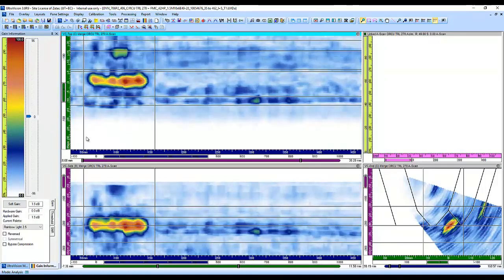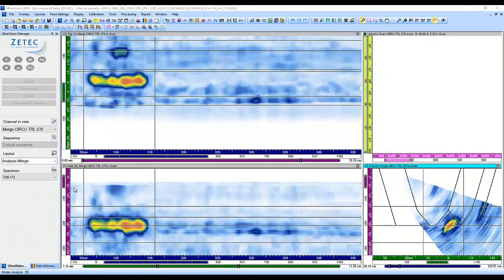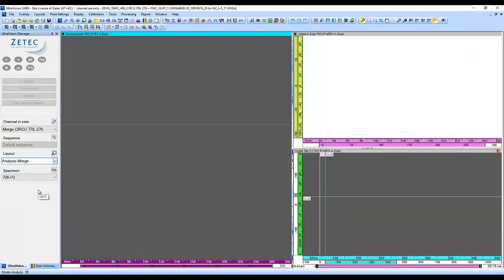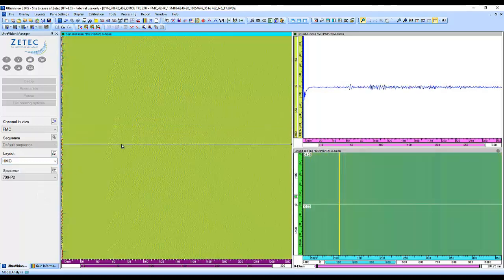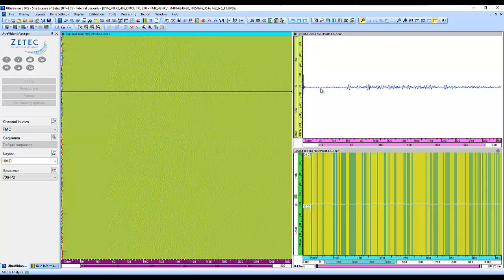The corner trap of the large crack is very well detected because the lower angles of the sector scan are typically focused near the ID. The upper part of the crack is visible and can be enhanced by using some soft gain, but the image is incomplete for this very high crack. We also recorded elementary FMC A-scans, and in the raw form, the data cannot be interpreted by the human mind — so processing is required.